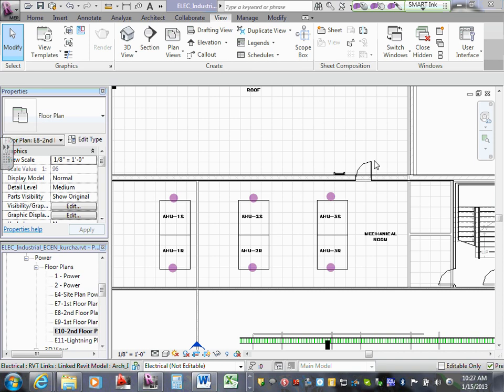So, for the return only? Just the return only, yep. How many did you say for the AH units? 2,000 CFM. Anything above 2,000 CFM. So roughly, what is that conversion? 1 ton equals 400 CFM. So anything above 5 tons is going to require a duct smoke detector.